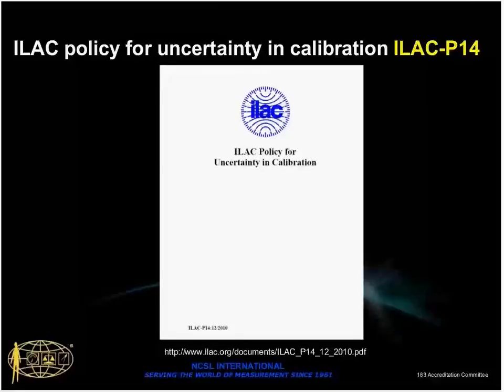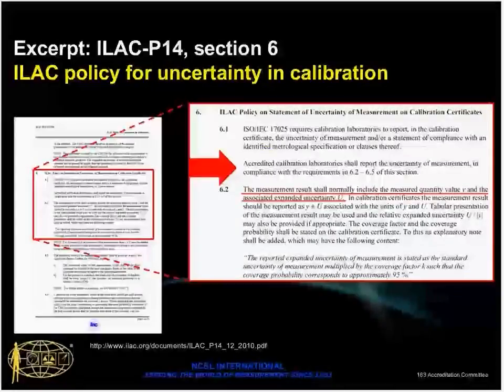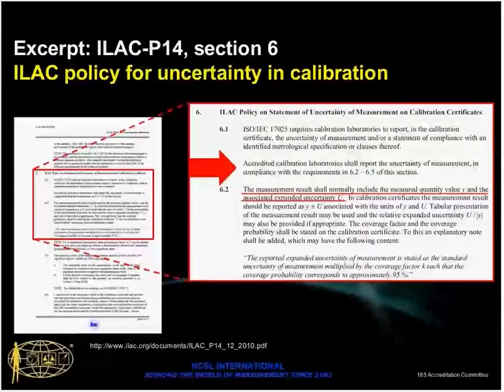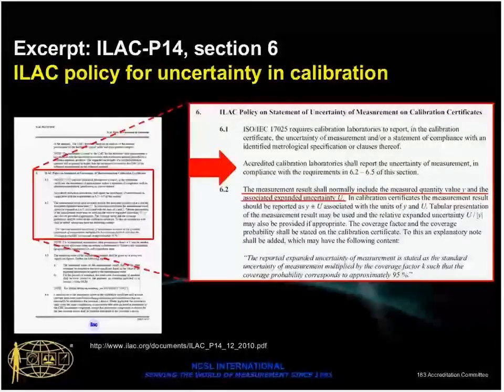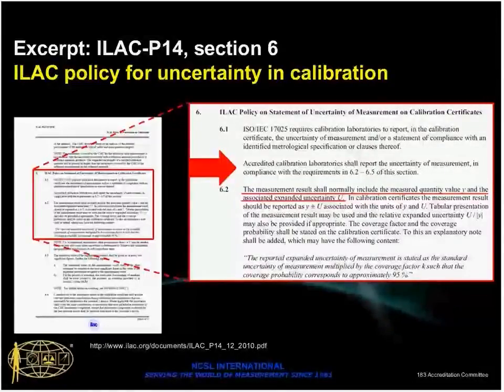The next area that we have to pay attention to is ILAC P14. And this is another document that ABs have to follow and enforce. But when we take a look at the specifics of ILAC P14, we want to focus on Section 6 of the document. Particularly in Section 6.1, the second sentence. Here's where we have the requirement that accredited labs shall report the uncertainty of measurement. And we can see the first paragraph is a restatement of 17025. But really, when we're taking a look at the second sentence there, the accreditation bodies are required to enforce that the laboratories report the uncertainty. As we look at sections 6.2 through 6.5, we can see that ILAC P14 has adopted the ISO GUM methodologies.